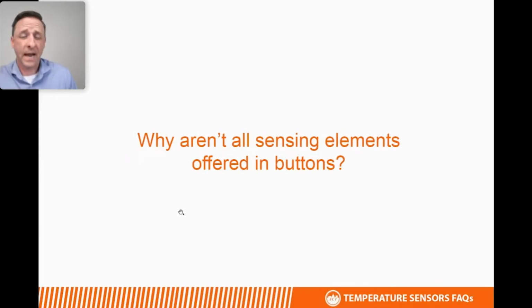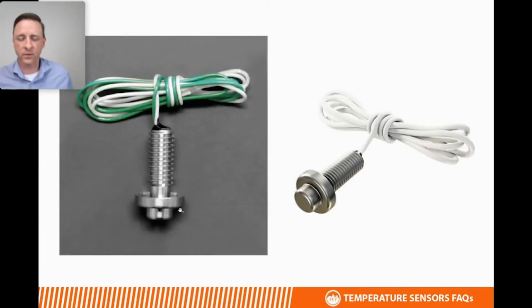If you look at the data sheet for our button sensors, you'll notice that not all of our standard thermistors are offered in the button sensor enclosures. That is because of the physical size limitations of the actual buttons themselves. So not all of the sensing elements that we offer can physically fit inside of those buttons, and that's why not all are offered in that specific configuration.